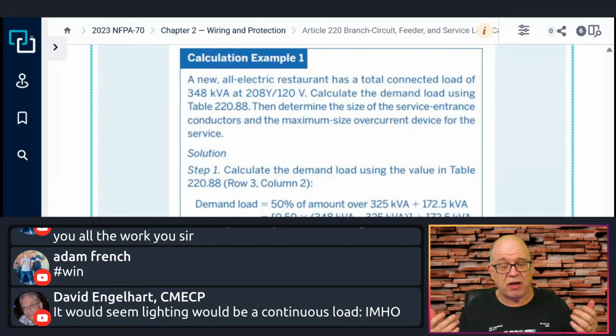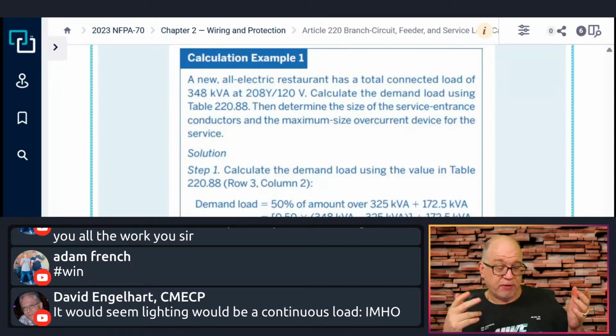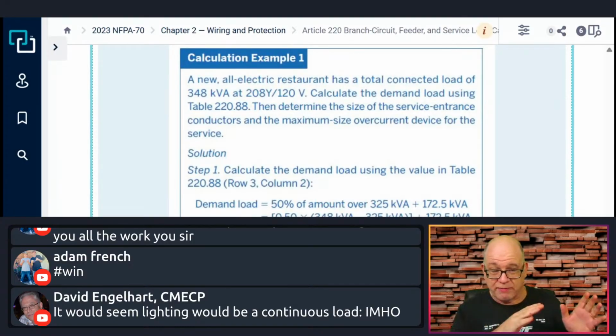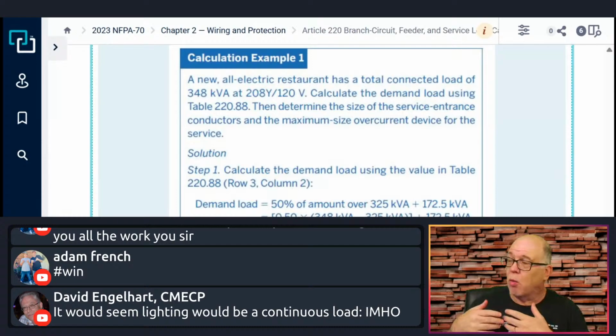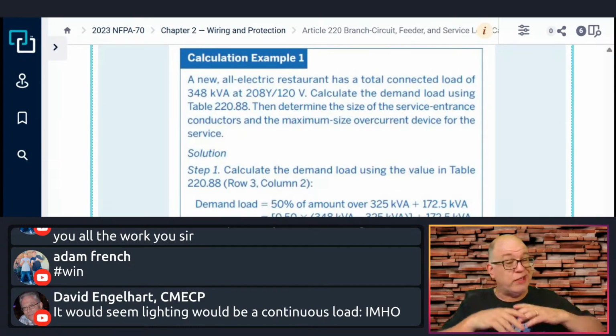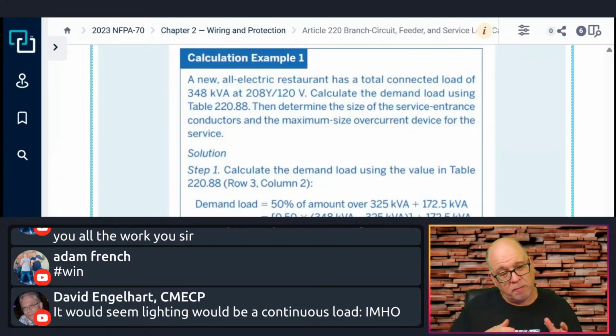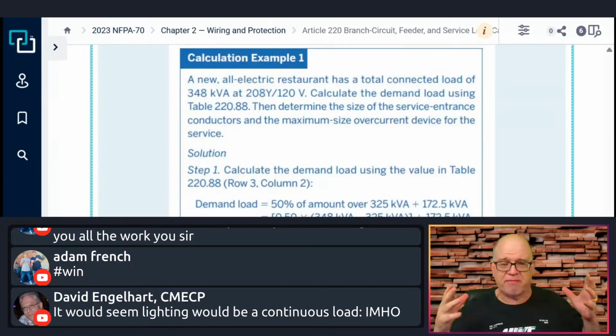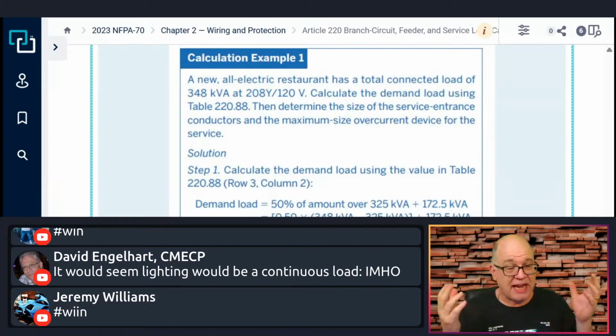And it's also taking all of those luminaires. Now, that doesn't remove you from sizing branch circuits to lighting for continuous loads. It's kind of like the water heater example: we size the branch circuit for continuous load, but when we do the load for the service, we don't size it that way. Same concept, and there's such a generous demand factor that the loads are so high that the optional method just says take every load at its total value and add it all together.